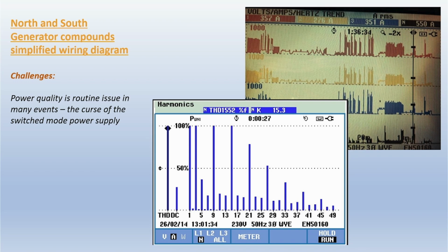This was the lighting rig for a particular artist. It had a lot of incandescent lamps being driven at about 50%. You can see the phases were not badly balanced, at sort of 360 amps, but the neutral current was 550. And if you stick 550 amps down a 400 amp connector, you can guess what happens. For those who deal in power, if you lose the neutral, it gets very expensive very quickly.